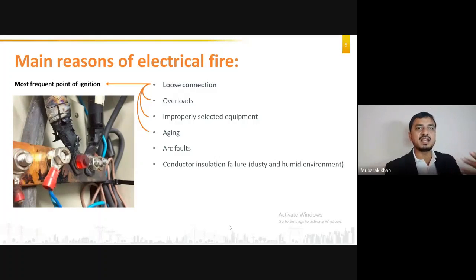Like if you select a higher load for a lower feeder, something like this, or aging, arc faults, conductor insulation failure, etc. Now the thing is that in case of overloads, aging or improperly selected equipment, when the system faults start, if your load is drawing a large amount of current, your system is bound to overheat, and which point will heat more? That is the point where the connections are loose.